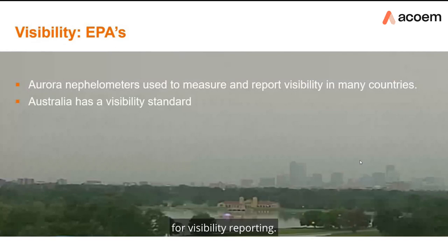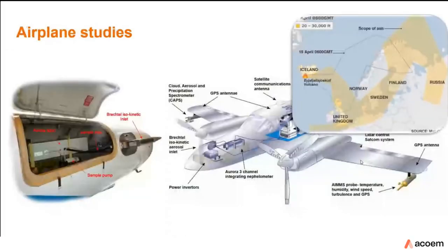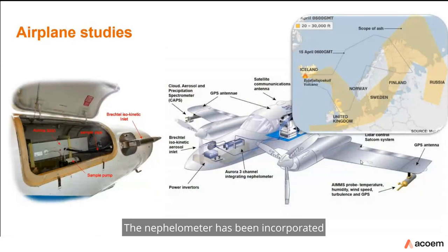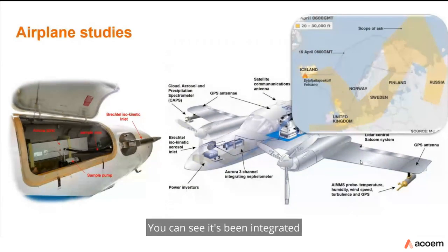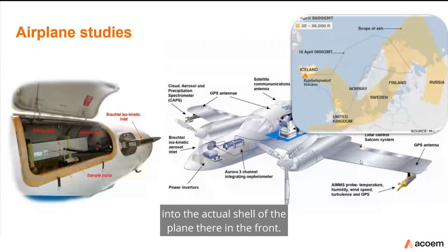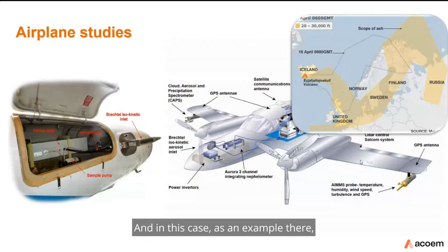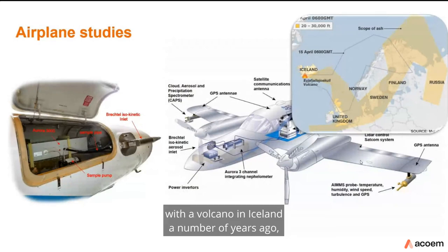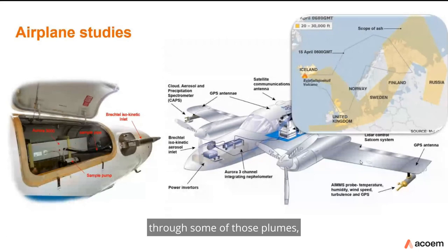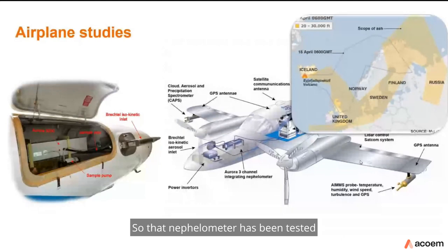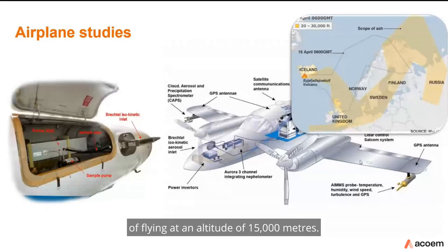The nephelometer isn't just ground-based — it has been incorporated into aircraft at different points over the years. One example is from the UK Met Office, where it was integrated into the shell of the aircraft. When a number of airlines were shut down due to the Iceland volcano eruption, that aircraft was still able to fly and take scattering measurements through volcanic plumes. That nephelometer has been tested to pressures equivalent to flying at an altitude of 15,000 meters.